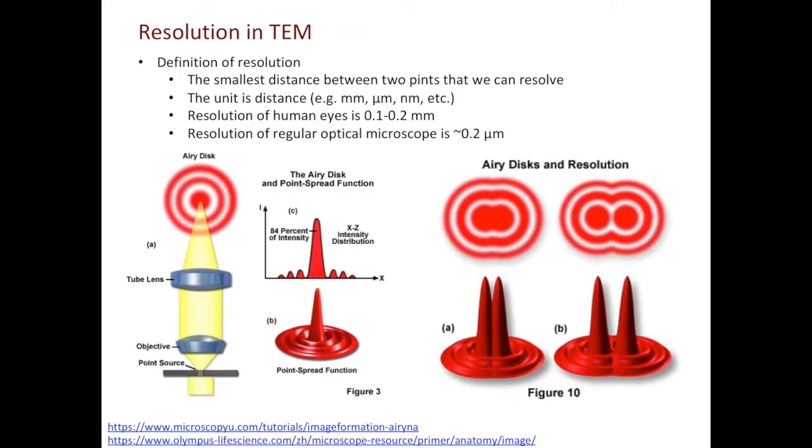After talking about why using electrons in TEM, let's talk about the resolution of TEM. The definition for resolution, regardless of the microscope you use, is defined as the smallest distance between two points that can be resolved. Therefore, the unit for resolution is distance, such as millimeters, microns, or nanometers. The resolution of the human eyes usually is 0.1 to 0.2 millimeters. The resolution for a regular optical microscope is about 200 nanometers. The resolution of TEM can be down to sub-nanometers easily.